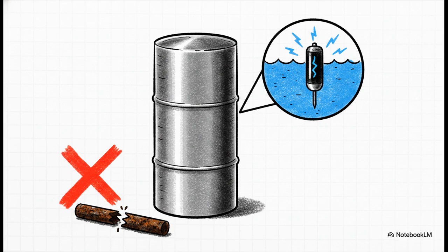Or, for glass-lined tanks, they're using impressed current cathodic protection, or ICCP. It's a specialized titanium probe that injects a precise, tiny microcurrent into the water. This perfectly counteracts the reaction that causes rust, effectively extending the tank's life indefinitely.